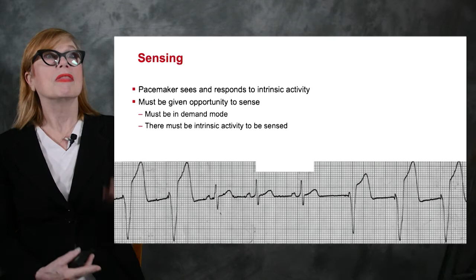So spike to QRS, spike to QRS, and that signal, that termination, is when the patient has his own beat. So the pacemaker resets its cadence, but the patient again has his own beat, so the pacemaker is not firing. Third beat in, and that's actually the fifth beat in, patient has his own beat and the pacemaker is inhibited. But then the patient does not have his own beat and the pacemaker spikes again, followed by a QRS, pacing spike, QRS, pacing spike, QRS. There must be true intrinsic activity in order to have sense. And that's really important. The pacemaker has to be able to sense that the patient has his own beat.